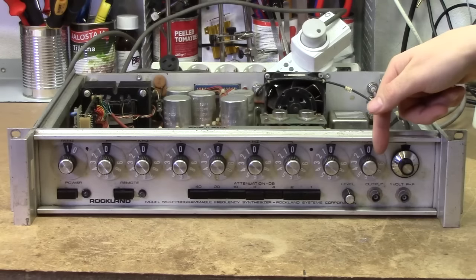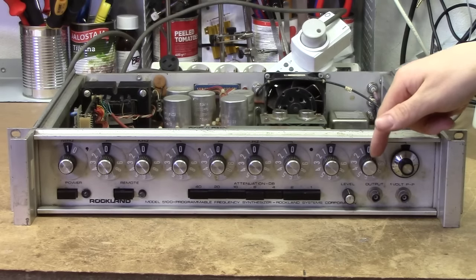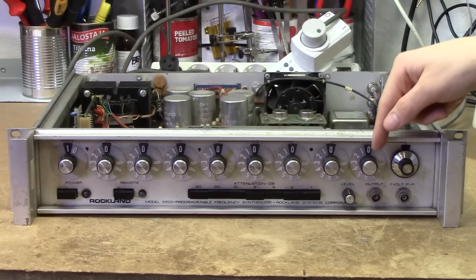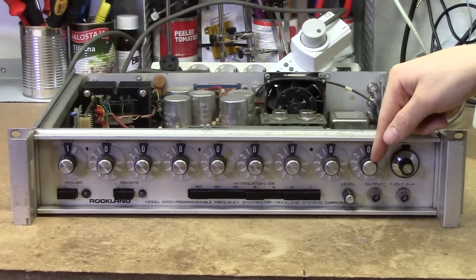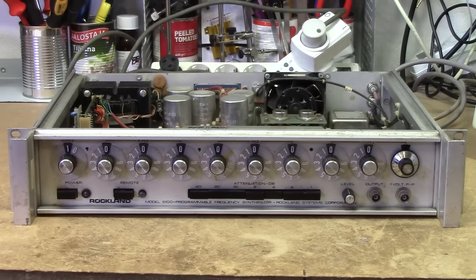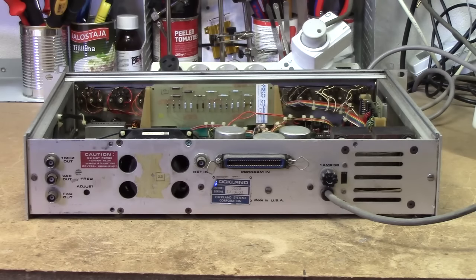We've got the remote button, which disables the entire front panel. But if you press the remote, it will actually stay on the last set frequency, which should be a given since it's a digital thing, and the acquire board just programs the DAC to perform a certain duty when you set the knob. And around the back, there really isn't too much going on either.